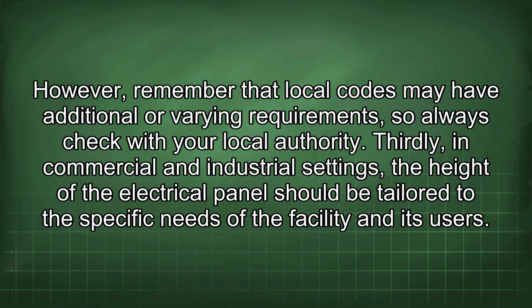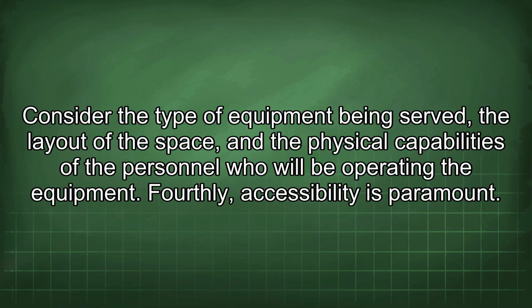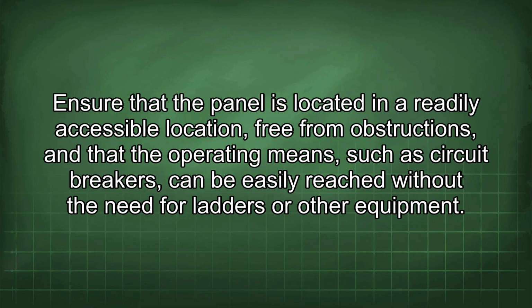local authority. Thirdly, in commercial and industrial settings, the height of the electrical panel should be tailored to the specific needs of the facility and its users. Consider the type of equipment being served, the layout of the space, and the physical capabilities of the personnel who will be operating the equipment. Fourthly, accessibility is paramount. Ensure that the panel is located in a readily accessible location free from obstructions, and that the operating means such as circuit breakers can be easily reached without the need for ladders or other equipment.